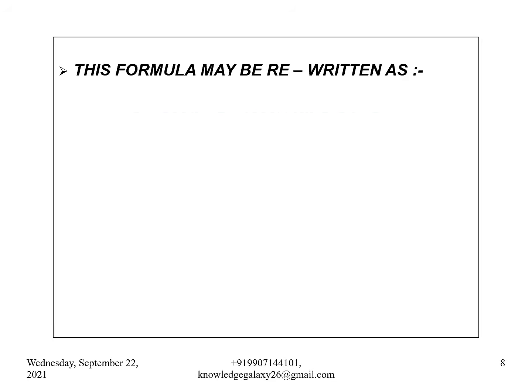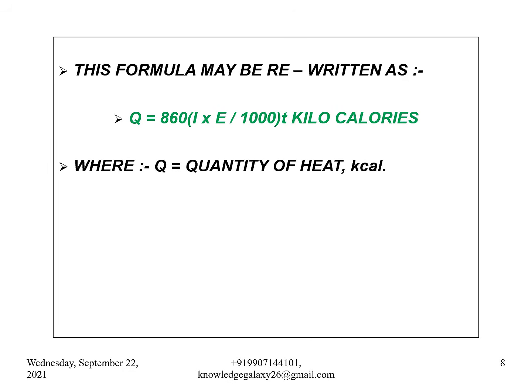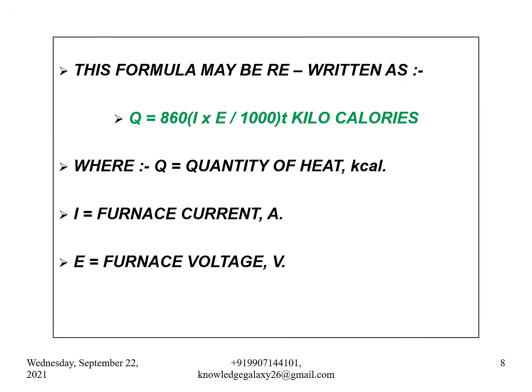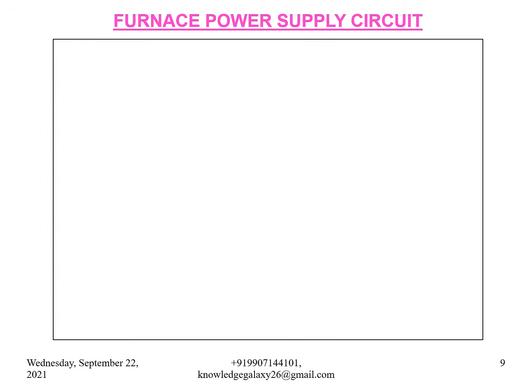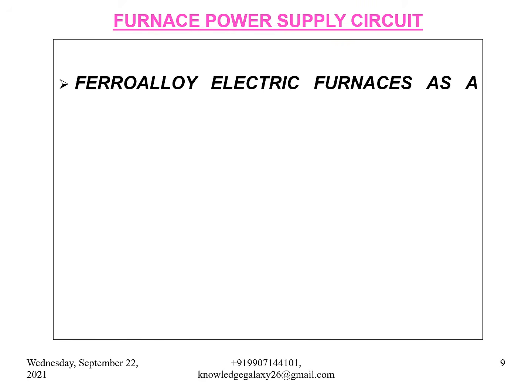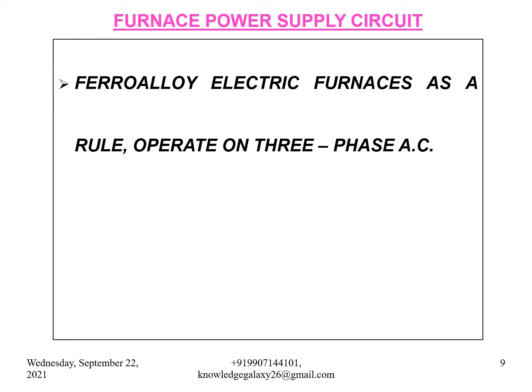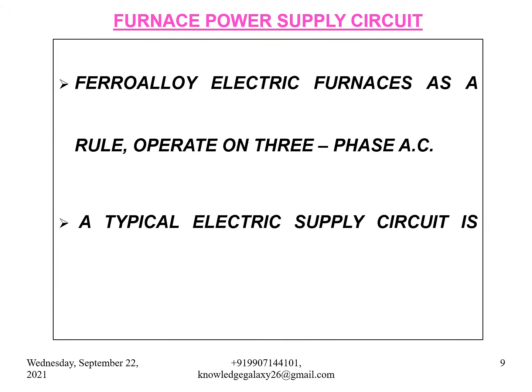My dear friends, this formula may be rewritten as Q is equal to 860 into I into E whole divided by 1000 into T kilocalories, where Q is the quantity of heat in kilocalories, I is the furnace current in amperes, E is the furnace voltage in volts, T is the time in hours. Furnace power supply circuit. Since a ferroalloy furnace is a powerful electrical unit, it is very much necessary and important to know about the furnace power supply circuit. Ferroalloy electric furnaces as a rule operate on three-phase alternating current. A typical electric supply circuit is shown in the next slide.